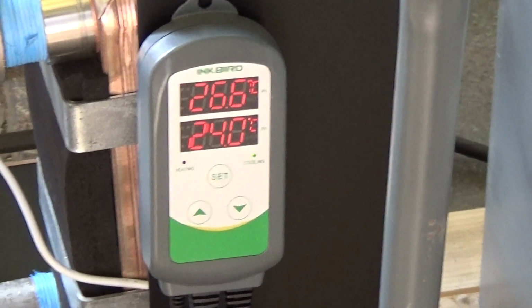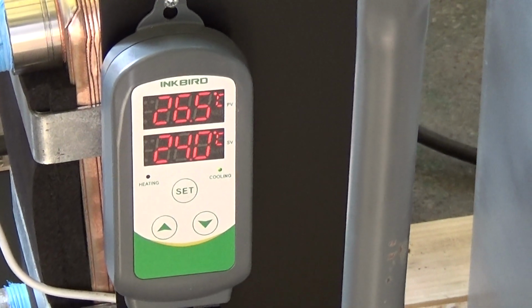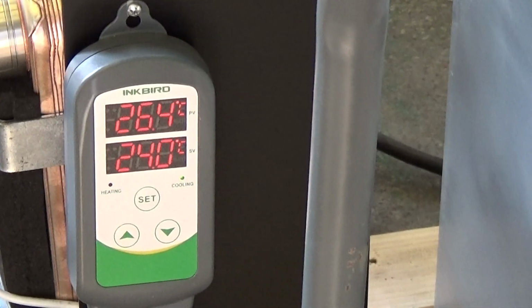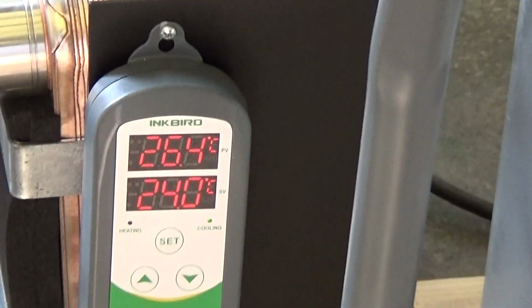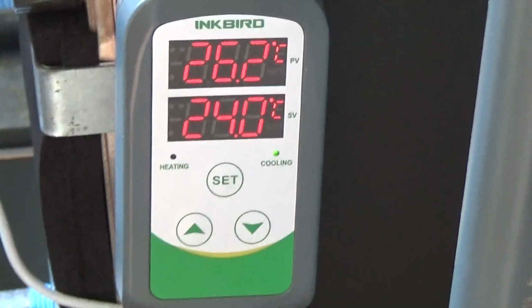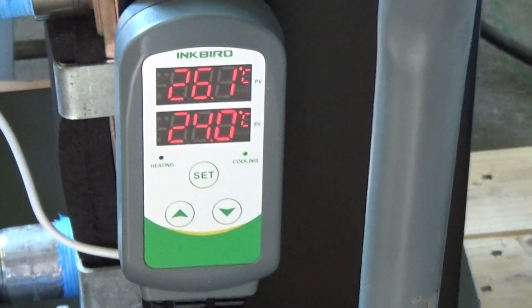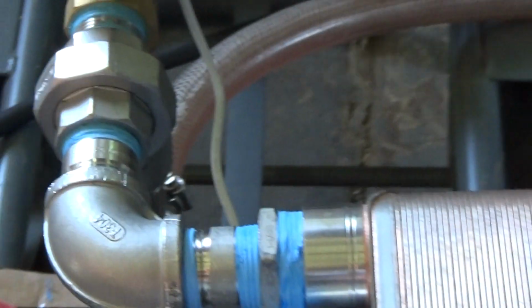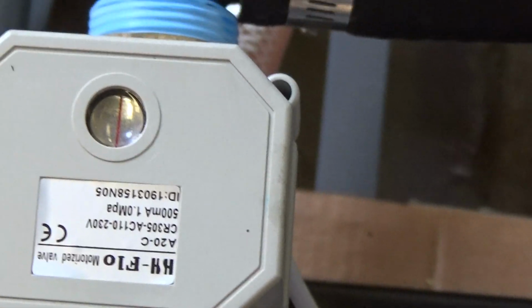So right now the Inkbird controller, which is set for 24C, is getting down closer to its set point, and it's basically calling for cooling right now, as you can kind of see that green light on. So right now, in that it's calling for cooling, this valve is open. The valve is actually open when you can see that little red line is parallel with the glycol inlet piping.